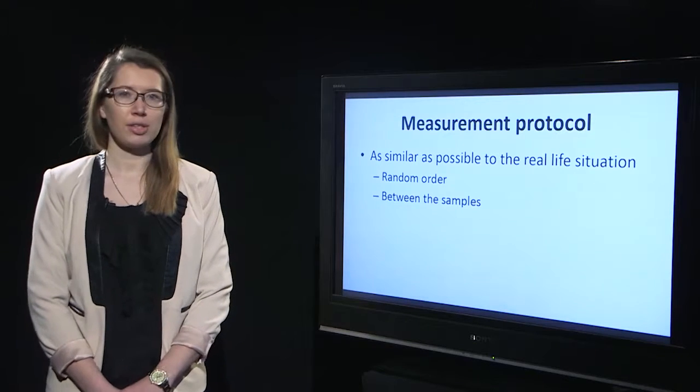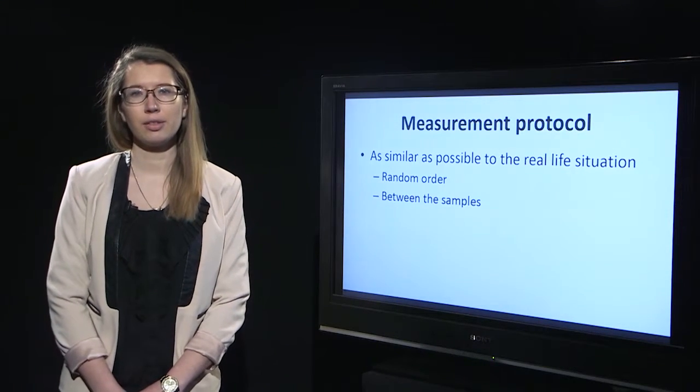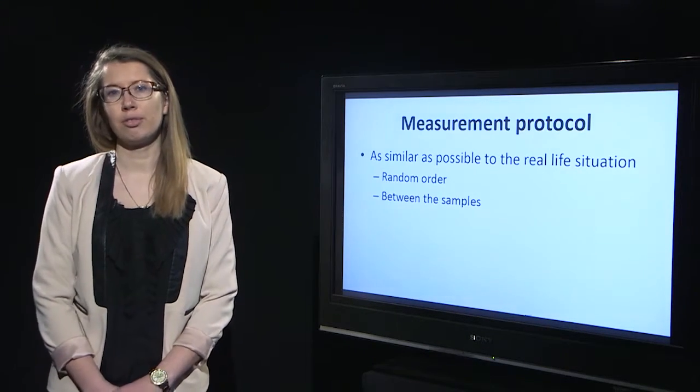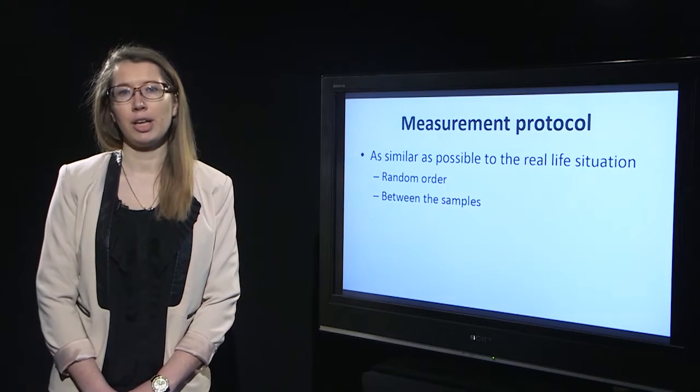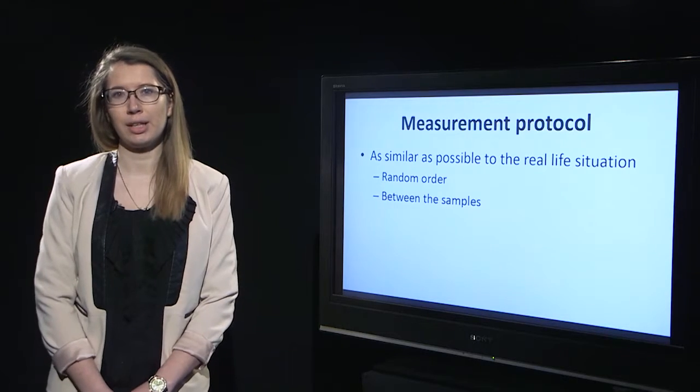It means the calibration samples should be analyzed in random order, in contrast to analyzing them in increasing concentration order. The calibration samples should be placed between the samples we analyze, so the instrument drift coming from, for example, the contamination of the ion source would be taken into account.